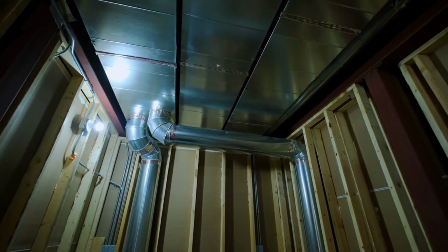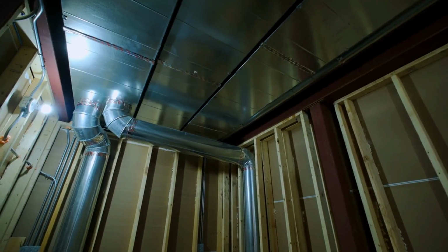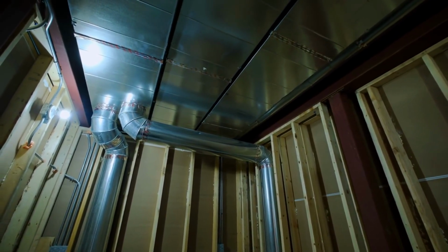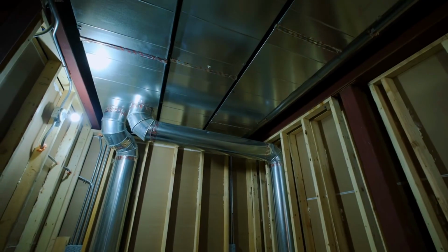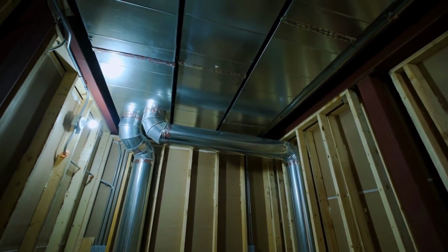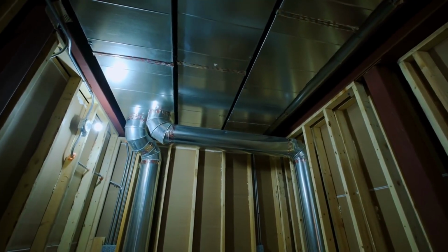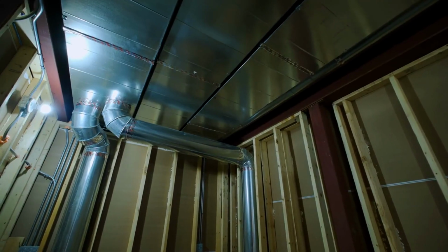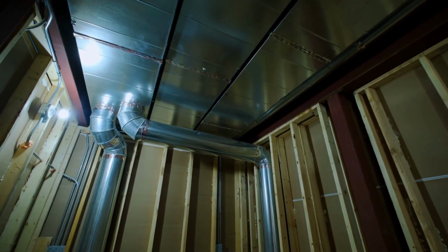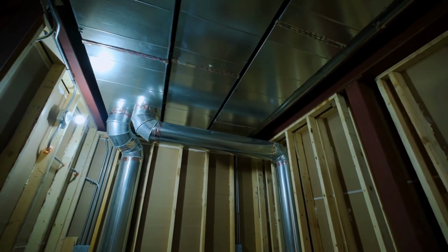Corridor exhaust. 1. For all projects, capacity or CIP, outside air supplied to the corridors must be exhausted by the toilet and janitor's closet exhaust fans. The outside air can also be exhausted by the combined central classroom, corridor multi-zone variable air volume, MZVAV, heat pump units or dual-temperature MZVAV units in new schools and major modifications. The toilet and janitor's closet exhaust systems may be combined.